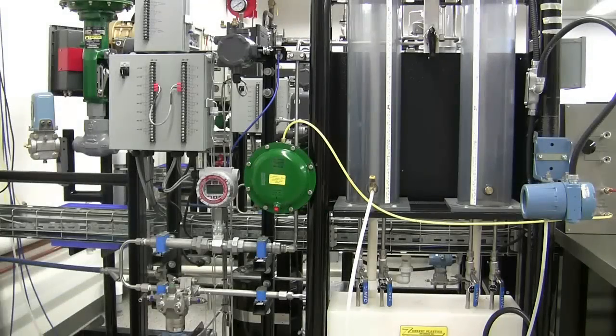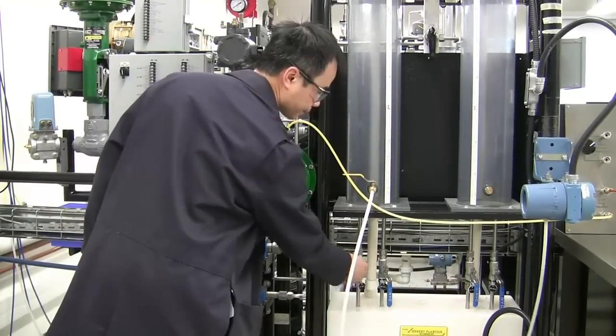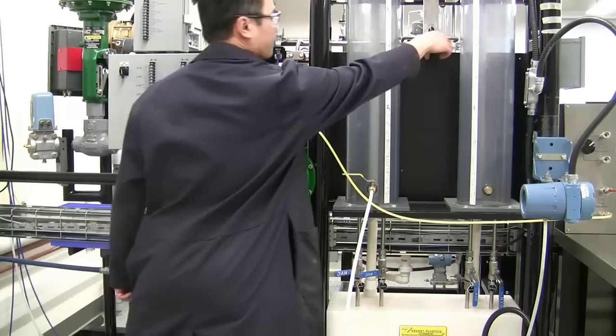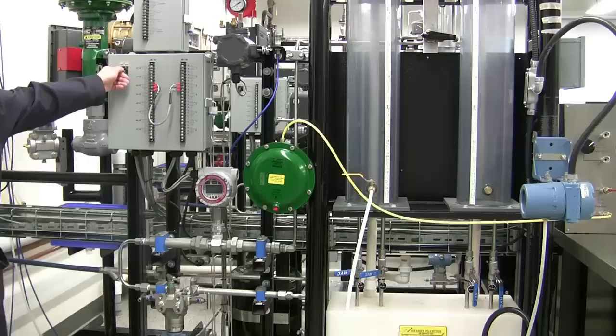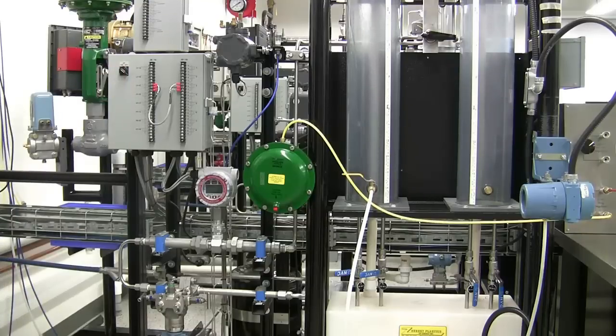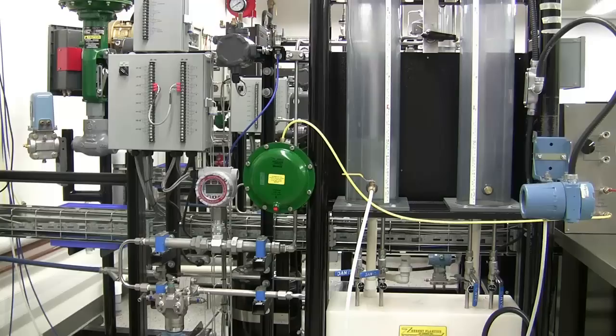The last thing before we allow water to flow into the tank is to close all the block valves and ensure that the 3-way valve is pointing to the tank we are measuring. Then open up the solenoid by turning the hand-off-auto switch to hand. Allow water to rise halfway up the tank, then switch the solenoid off.